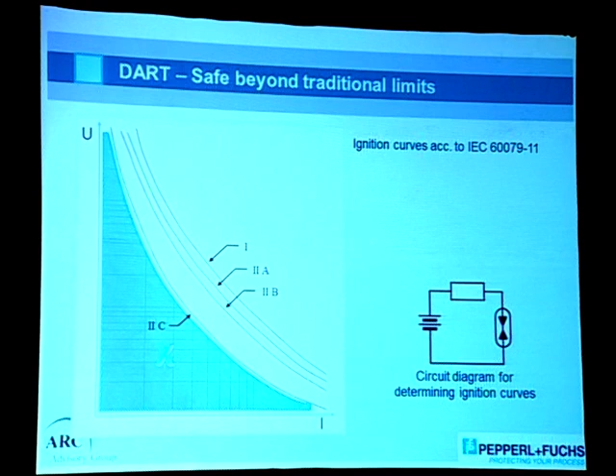When we select a power supply voltage, for example Entity or FISCO, it always lies in this region. But this is not good enough for a Fieldbus or digital applications. So now what we do is move to the other side, and this is what we're doing in the new type of intrinsically safe design. We think from the other side, the higher power side, and figure out how to design the safety circuit and make sure intrinsic safety is achieved.